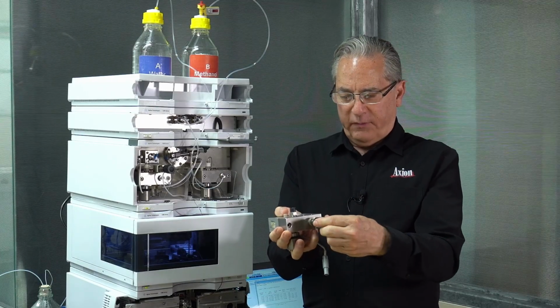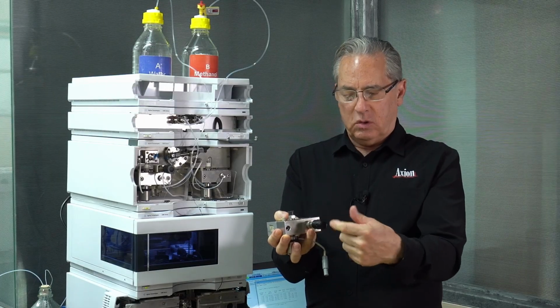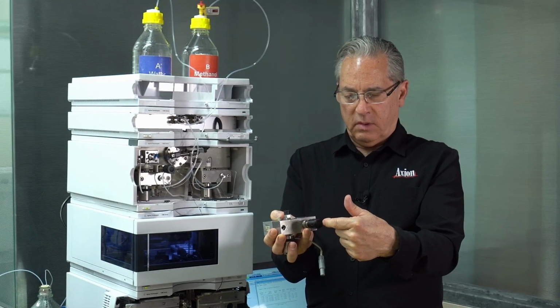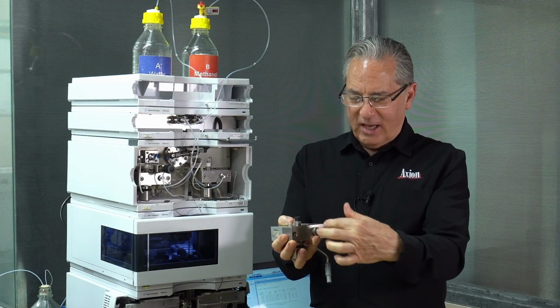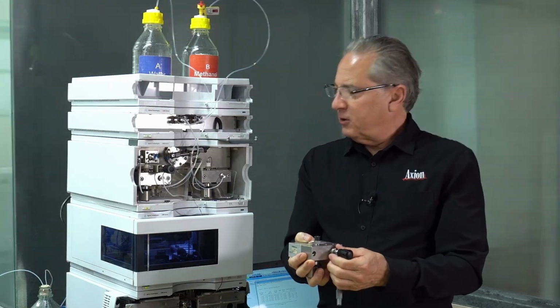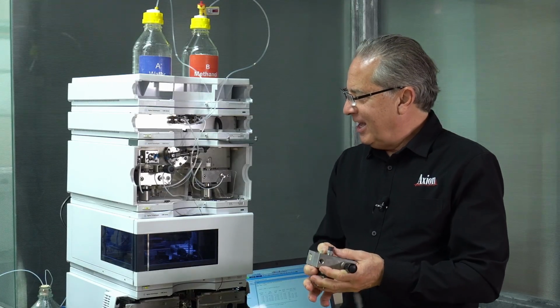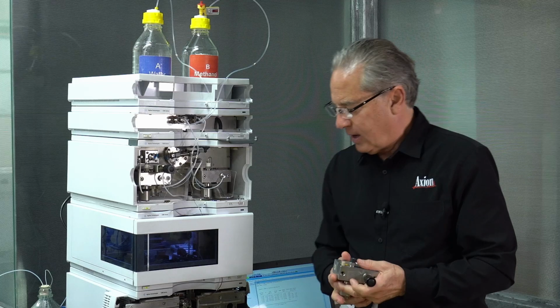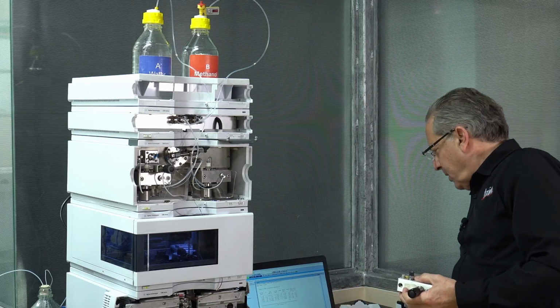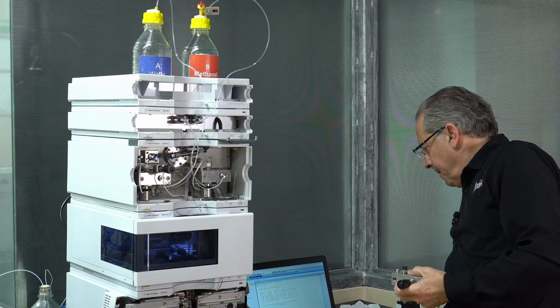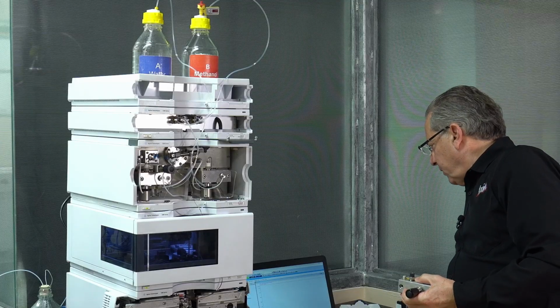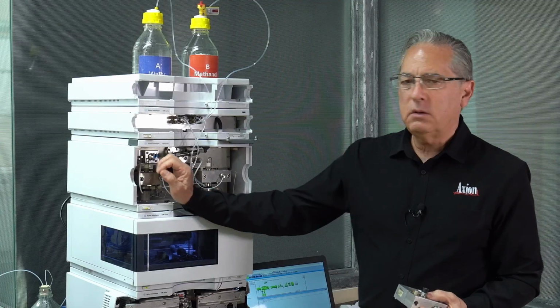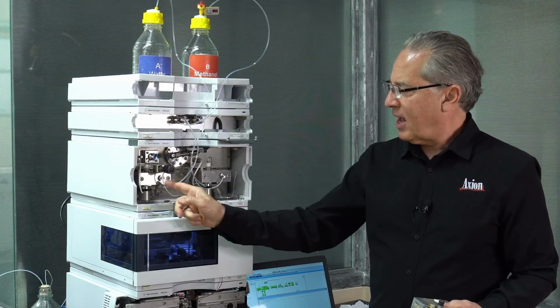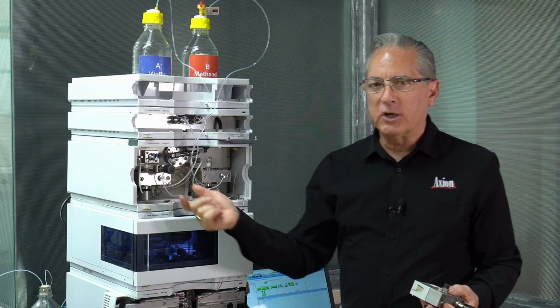This is the purge valve up front, right? This is what we open and close to send the output straight to waste. Now inside the purge valve, there's a little filter. And what's interesting is, if you were paying attention to my current HPLC instrument, if I open the purge valve, the pressure should go to 0. In theory, right? Because I'm pumping through this hollow piece of tubing, I should have no pressure at all.